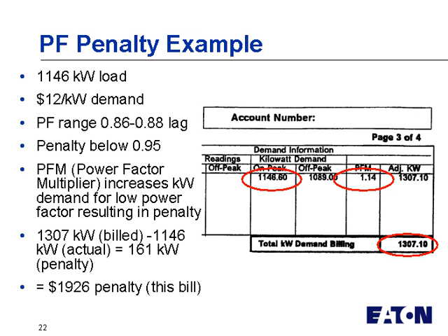Now let me give you an example, and I tell you this is a real life example. It just happens to be from the building I'm standing in right now, and so nobody's immune to this hidden charge. We kind of looked at our bill when we built this building about 5 years ago, and it was in the winter, and we didn't think we had a penalty. Well, as it turned out, in the summer, power factor dropped to about 0.86, and that was below the actual level that the utility requires, which is 0.95. And you wouldn't even think that that's much of a substantial penalty, but it turned out that it was about $2,000 a month just on this bill.